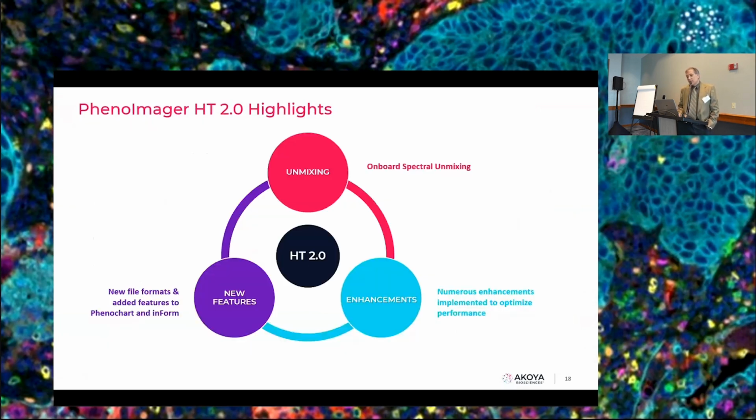On the HT side, you heard a couple folks talk about how the scanning goes fairly quickly. But the way in which we image up to 8+1, or in a whole slide basis 6+1, is through spectral unmixing. We image the sample with cleverly chosen filters and then do spectral deconvolution so we can assign the energy to the proper channel and get rid of any crosstalk, and just as important, isolate autofluorescence and largely remove that from the signal so that you get quantitatively good data.